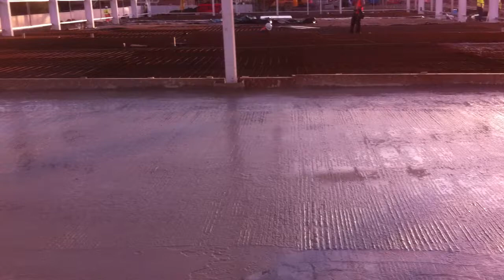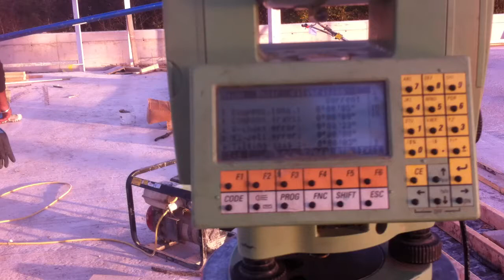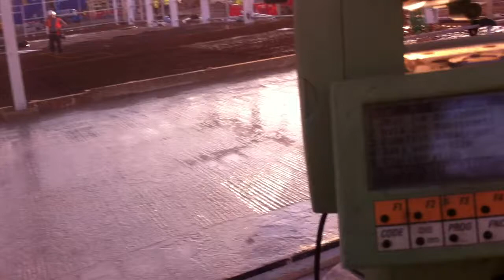So what we got here on the instrument now, going back again, is 5 seconds and 9 seconds. So I'm going to accept them new values, okay? And right, okay, they're accepted. Now then, what I'm going to do with the machine is I could go on testing it all day. I've only added that part of the test just to show that the instrument has got this facility and it's not on your cheaper instruments. Hence, I think this type of work is only good for instruments of this sort of quality and standard. Right, okay.